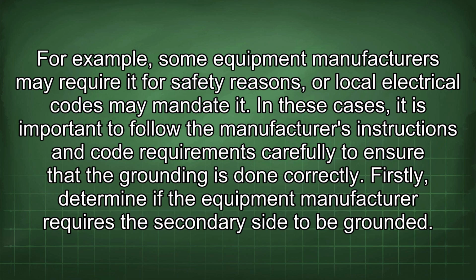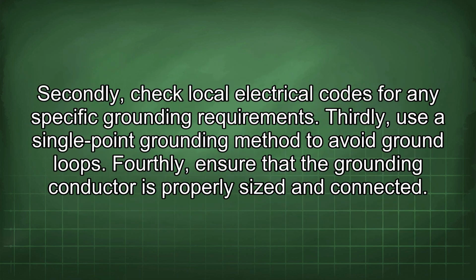For example, some equipment manufacturers may require it for safety reasons, while local electrical codes may mandate it. In these cases, it is important to follow the manufacturer's instructions and code requirements carefully to ensure that the grounding is done correctly. Firstly, determine if the equipment manufacturer requires the secondary side to be grounded. Secondly, check local electrical codes for any specific grounding requirements. Thirdly, use a single point grounding method to avoid ground loops.